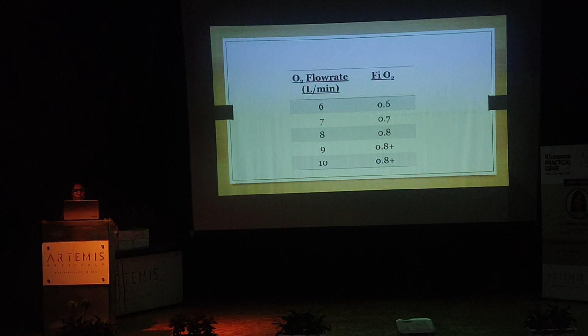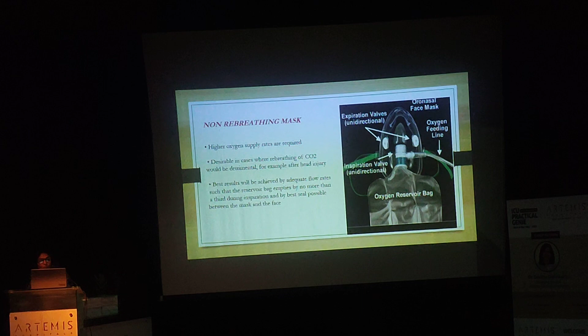Now the non-rebreathing mask. The non-rebreathing mask is different from the rebreathing mask. For the expired gases, there is a one-way valve, so the gases exit through that one-way valve, and there is no mixing of the inspired and the expired gases because there is a valve between the reservoir bag and the inlet. It is provided with one-way valves between the mask and the bag and also at the exhalation ports. An FiO2 of 95% can be achieved with an oxygen flow rate of 10 to 15 liters per minute. So higher oxygen supply rates are required for this.